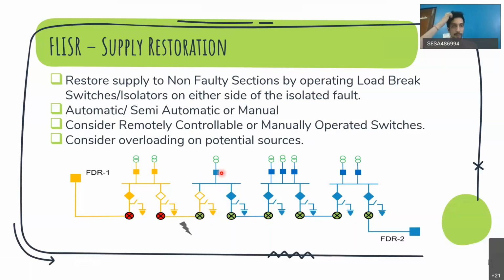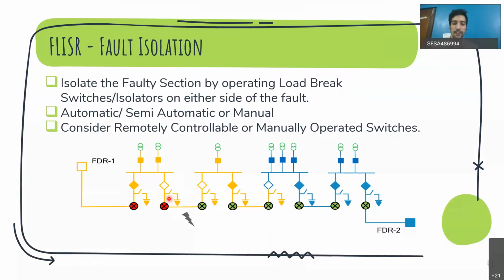Then supply restoration: restore supply to the non-faulty section. We have isolated the fault here, so we can restore supply to the non-faulty section on this side and this side, both sides of the fault. That can be done by closing back the feeder breaker. Since the fault is isolated, it will not retrip again. So this side supply is restored.